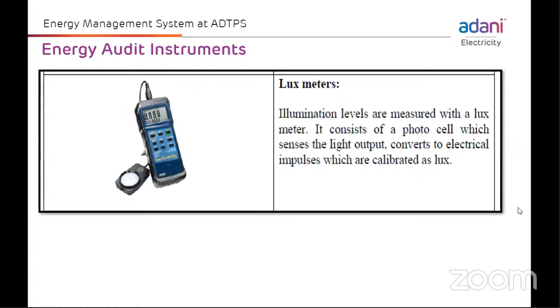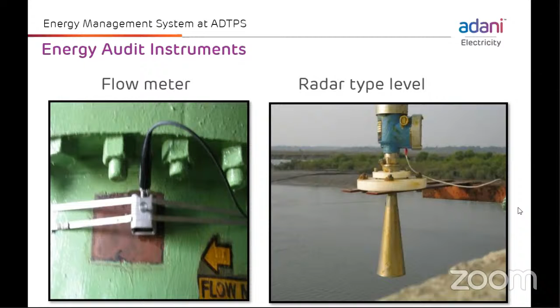This is one of the flow meters installed in our CW piping, and right one shows the radar type level indicator, which we are using for the sea tide level, because we are using sea water as a cooling water for our condenser cooling, and depending upon the tide level, we are either switching on or switching off the cooling water pumps to optimize our auxiliary power consumption. Because whenever there is a high tide, there is sufficient amount of suction available for the pumps, so we can switch off one of the pumps and will be able to maintain our condenser vacuum with remaining pumps, and thereby reducing the auxiliary power consumption.